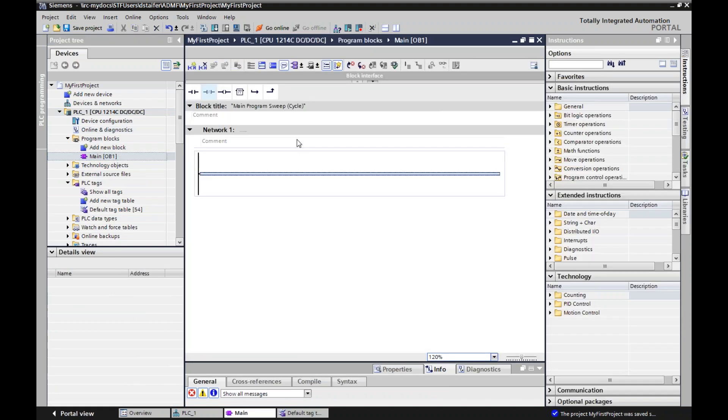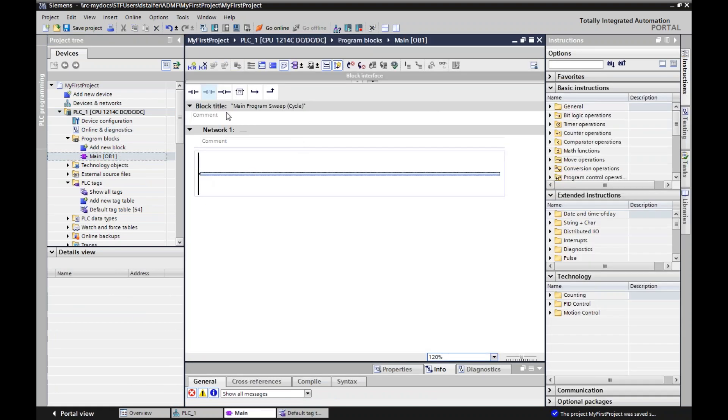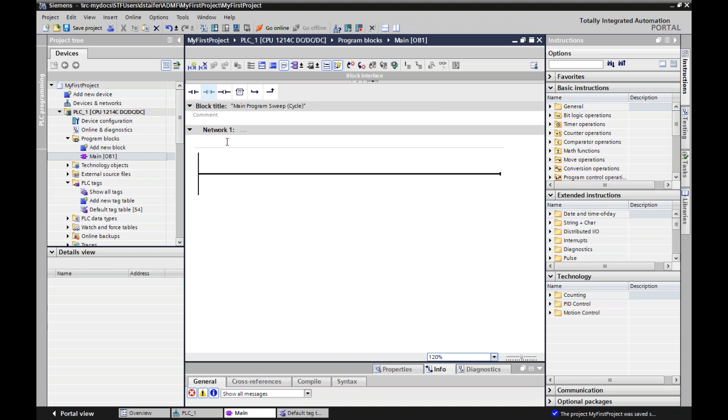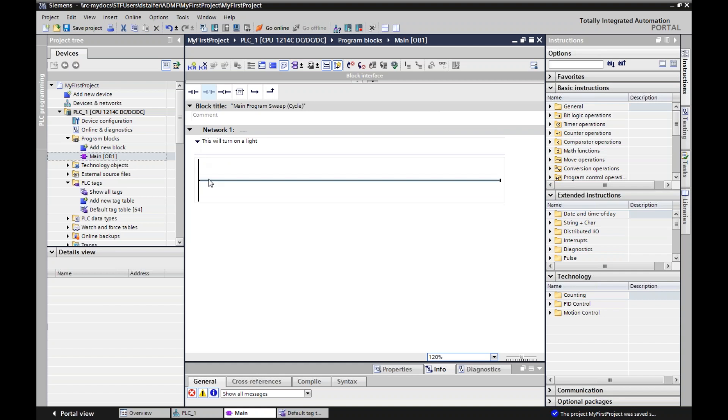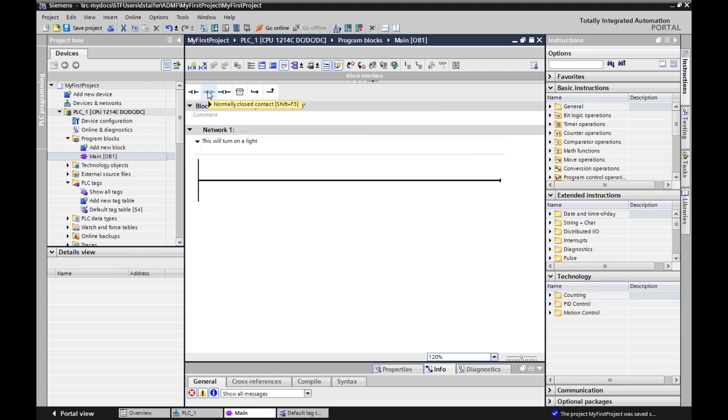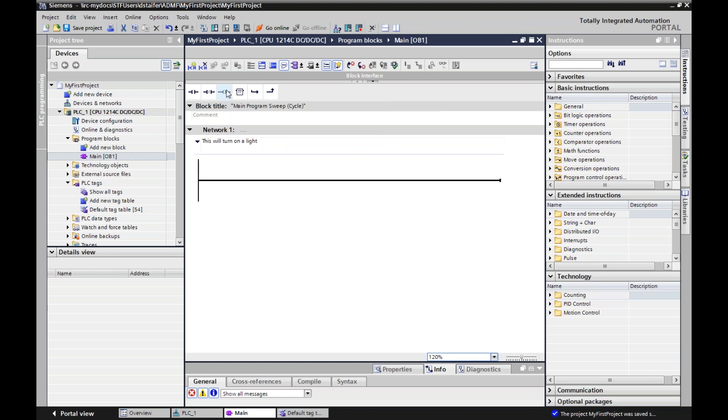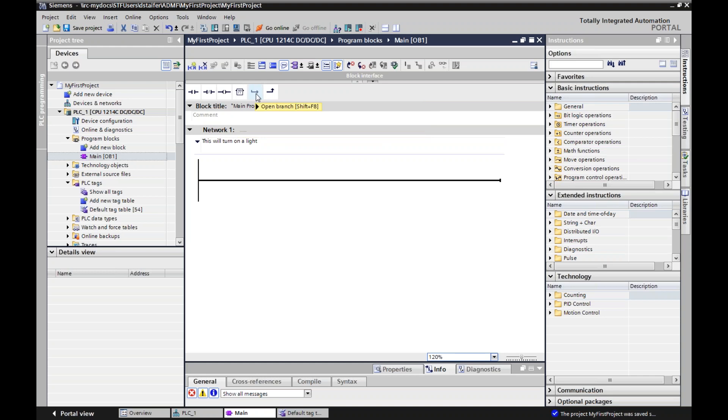So let's go back to our main operating block, and here's my network. I can do a block title for the whole program. I can make comments here. This will turn on a light. So there's my basic network. Now, this is a rung. This should look like fairly simple ladder logic. And if you look up here, that should look familiar. I got my normally open contact. I got my normally closed contact. Now, remember though, when we're programming, that's logic, normally closed, normally open contacts. So be careful. And I got my assignment or output coil. This is an empty box. More on that later. And this is how I open a branch or close a branch.